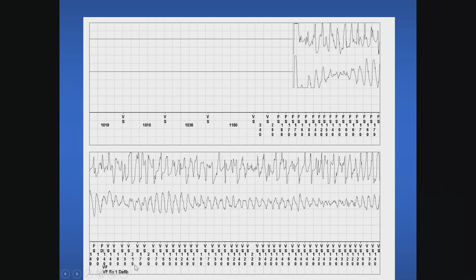So the Achilles heel of this system is really the wire that connects the can to the heart. That wire can sense noise from outside electrical sources, something called electromagnetic interference. It can also break if the patient is very active, or if the lead is old, or if it's defective in some way. So here's an example of a patient that has noise from their lead. When we look at this surface ECG here, we can see with our mind's eye that there are beats here, but there's a lot of shaggy electrical signal superimposed on the beats that is electrical noise.